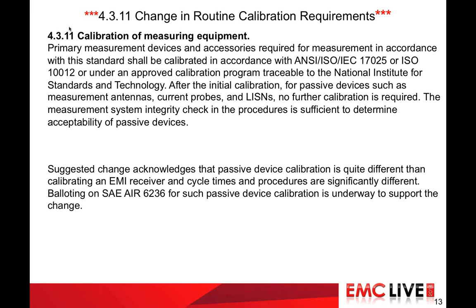Okay. MIL Standard 461 is somewhat unique in requiring end-to-end checks of measurement setups prior to each measurement. This is a much better approach than relying on routine periodic calibration of individual pieces of test equipment. The idea of this change is to de-emphasize formal calibration of passive transducers and even active ones that are routinely checked during every MIL Standard 461 test, and also easily checked using calibrated test equipment owned by an EMI test facility. So for instance, EMI receivers, spectrum analyzers, oscilloscopes, and electrically short field sensors are all items which must be routinely calibrated in a NIST-traceable manner.